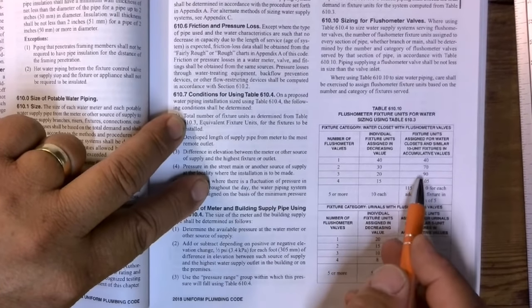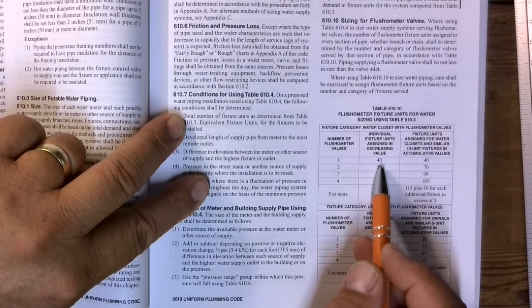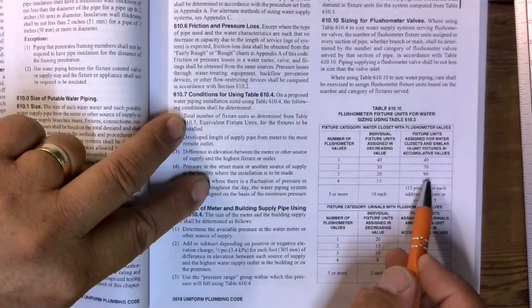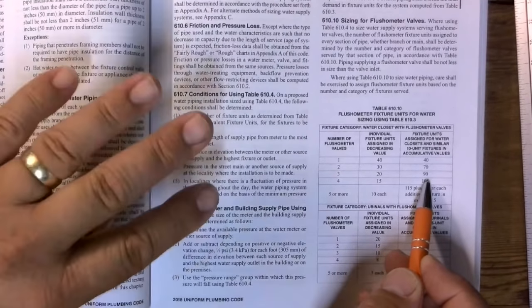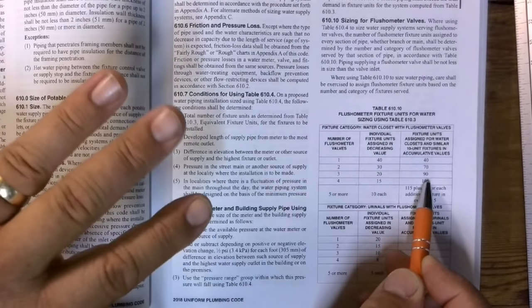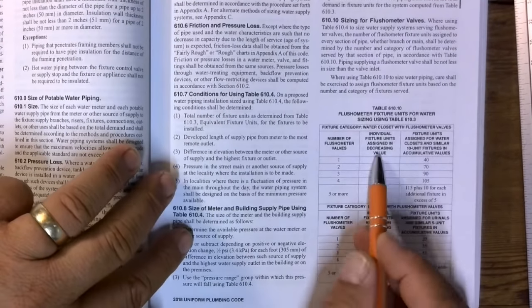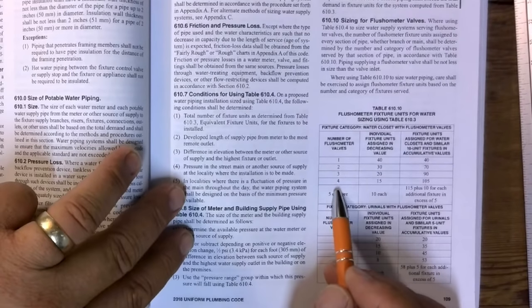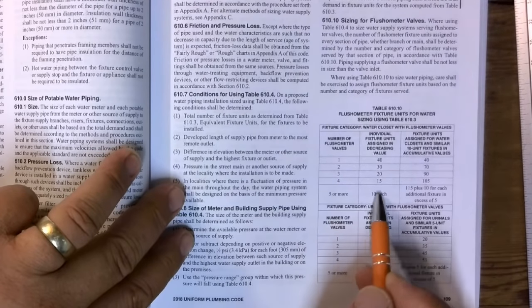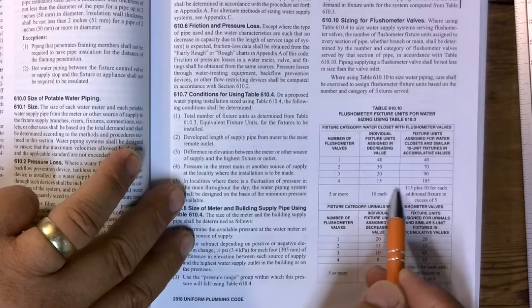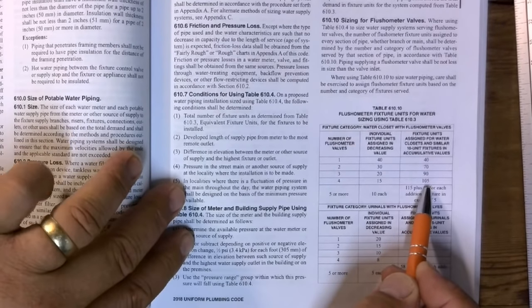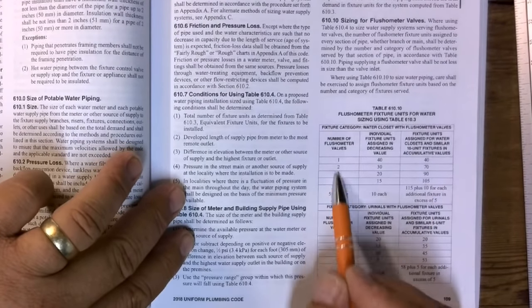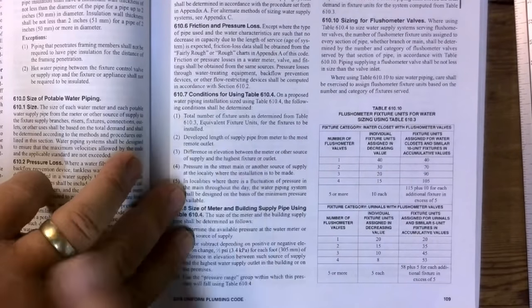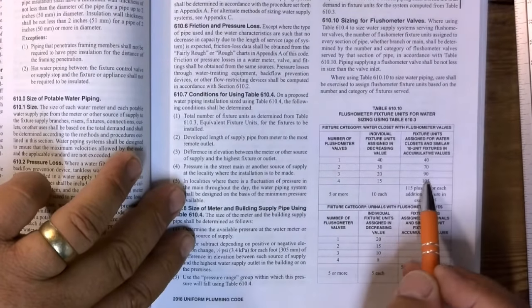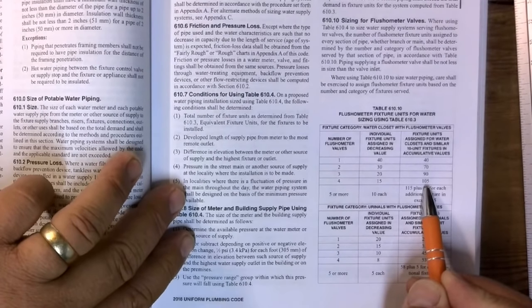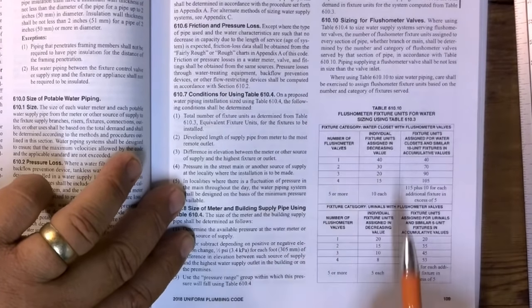So you can see that it's decreasing in value, because if you did 40 per and you're at three, it should be 120. But because you're operating three flush valves, the fixture unit value is going down. Four flushometer valves, the fourth one is 15 fixture units, a total of 105 fixture units for that one piece of pipe. So I have four water closets running on the same line, on the same wall, and a fixture unit value of 105 when all four are piped in there.